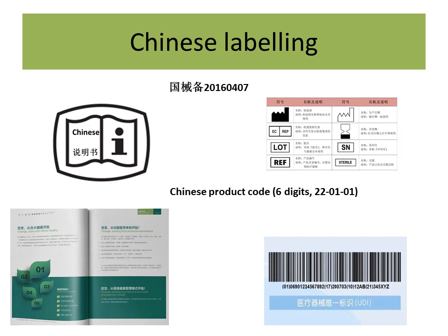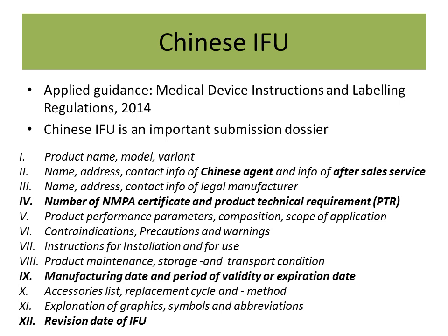The unique items, for example in China, are certification number and 6 digits product code. You need Chinese IFU at product registration submitted to Chinese authority. It is not that simple to translate once at the beginning from original language immediately to submission version. There are many contents to add, revise or even remove for the appropriate Chinese product variant.